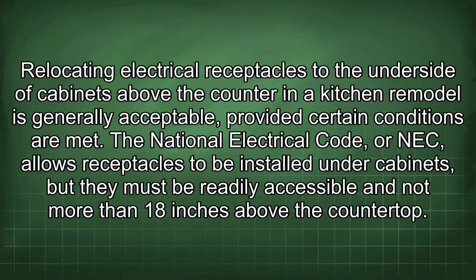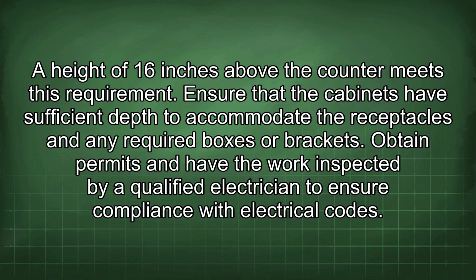Relocating electrical receptacles to the underside of cabinets above the counter in a kitchen remodel is generally acceptable provided certain conditions are met. The National Electrical Code, or NEC, allows receptacles to be installed under cabinets, but they must be readily accessible and not more than 18 inches above the countertop. A height of 16 inches above the counter meets this requirement. Ensure that the cabinets have sufficient depth to accommodate the receptacles and any required boxes or brackets.